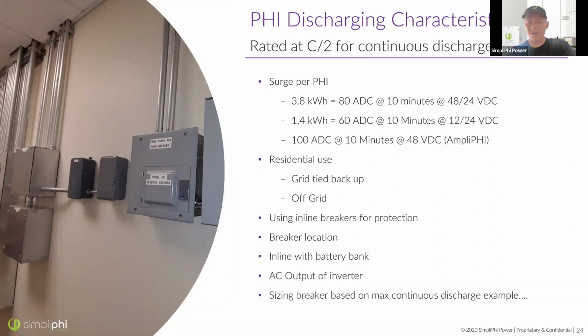Realistically, I rarely see these surges being used for more than a couple of milliseconds to start a well pump or a motor for maybe a saw. So it's unlikely that you're really going to be using these in a residential application. This is honestly more geared toward maybe businesses that have peak power demand charges and they just need to shave off an extra amount of power for a couple of minutes here and there.